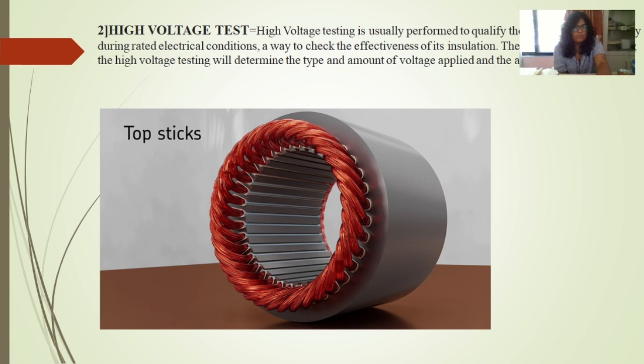The second will be the high voltage test. High voltage test is usually performed to qualify the device to operate safely during rated electrical conditions, a way to check the effectiveness of its insulation. The objective sought during the high voltage test will determine the type and amount of voltage applied and the acceptable current flow. You can observe the diagram.